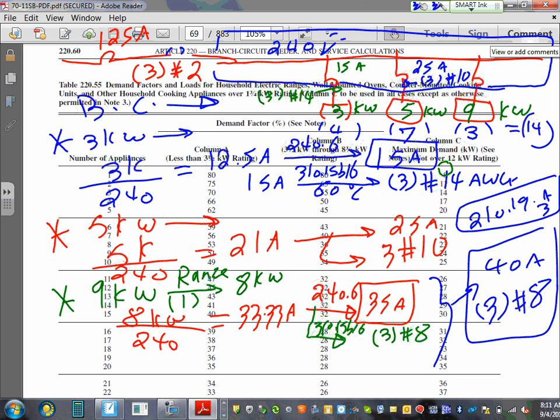Because of the exception. Again, sorry guys, I only explain the code, I don't write it. But the rule that you apply continues to be the same. Everything's cool, but there's an exception that says if your range is 8 3/4, which mine is, what was mine? 9. 8 3/4 or more, regardless of what your calculation comes up with, your branch circuit cannot be less than 40. So we were very close though. That's where this ends up with 40. So this will be 40 amp, and these will be 3 conductors, number 8.